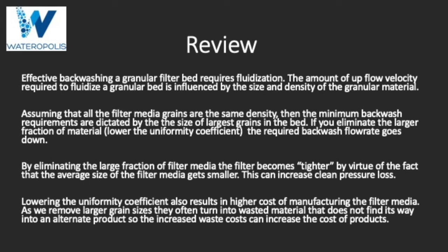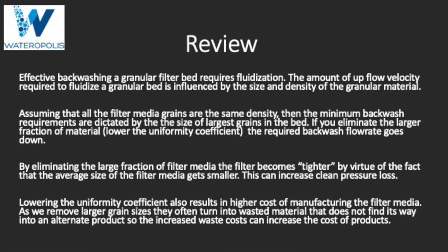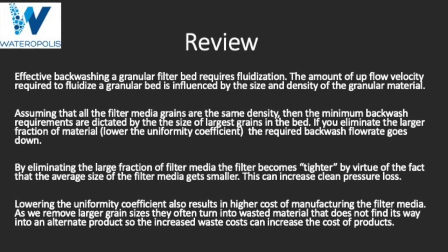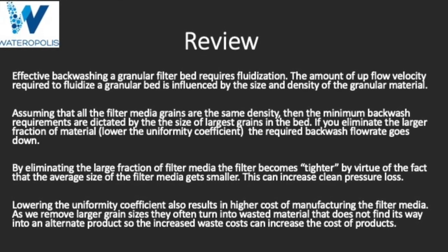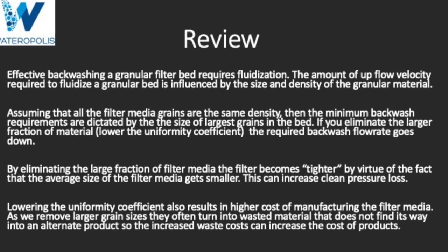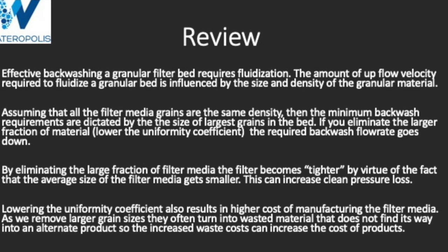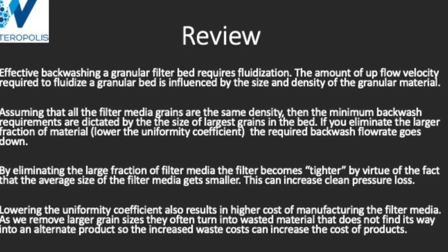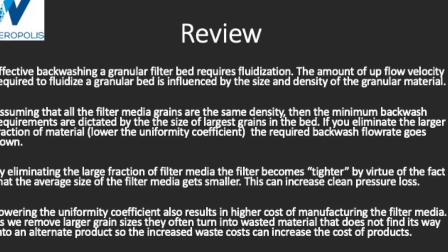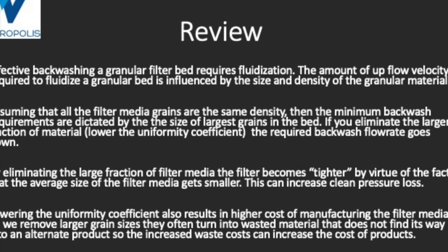Some things to keep in mind. Make sure that the vendor of granular material is using a set of consecutive sieves without significant gaps in sieve size. The closer the sieve value from screen to screen, the more accurate the sieve analysis. Lowering the uniformity coefficient reduces the size variation of the granular mixture by scalping out the larger grain material. This elimination of larger grain content lowers the average grain size in the bed overall. This reduces backwash rates but can have a negative impact on the cost of production.